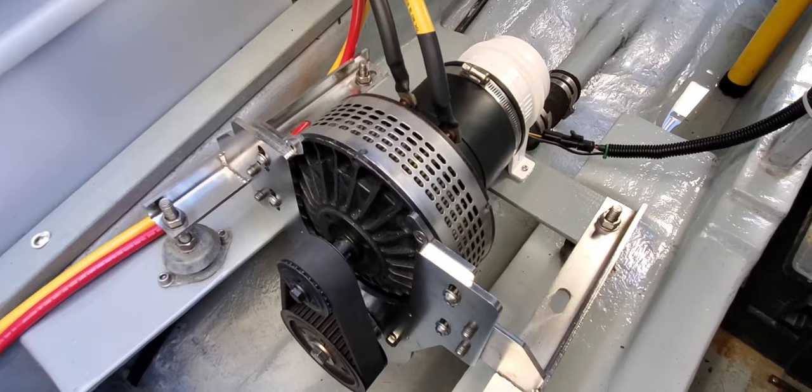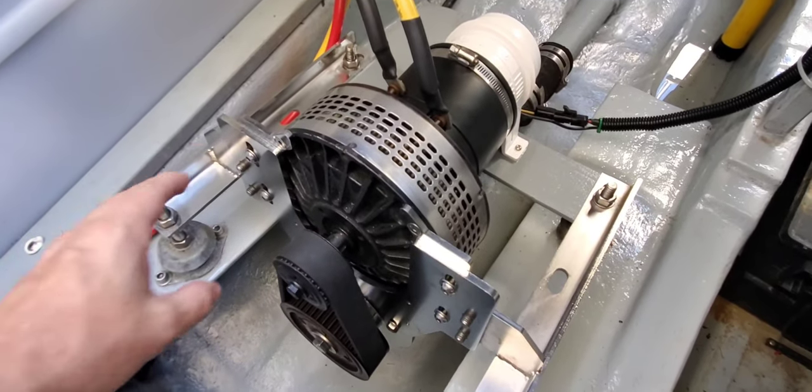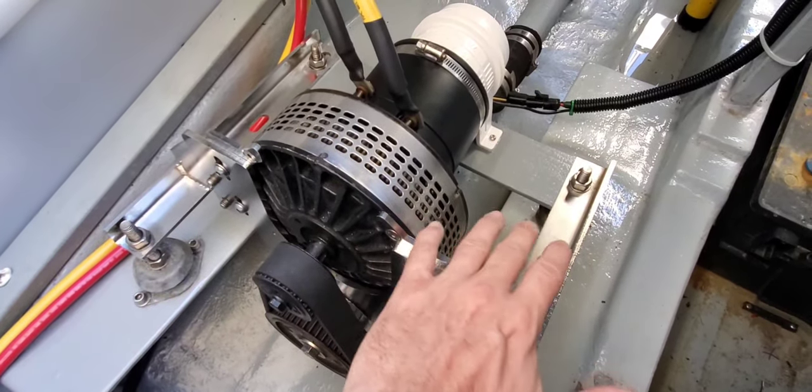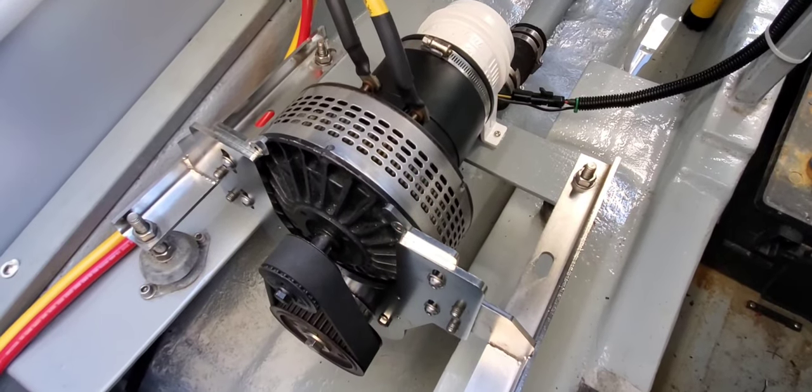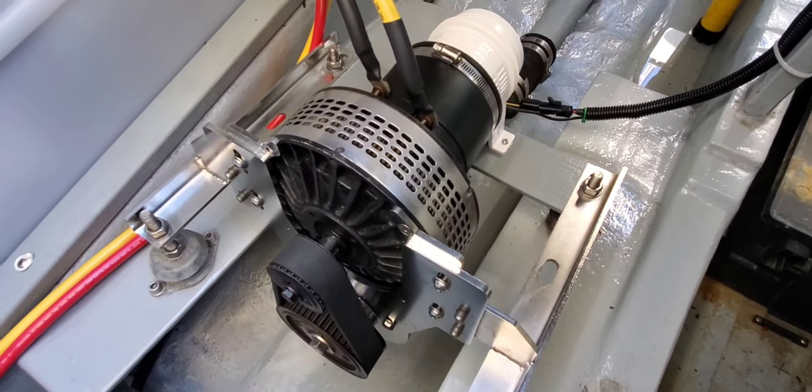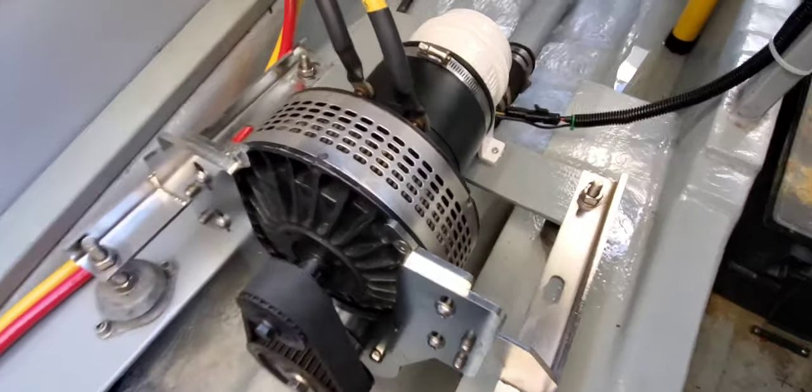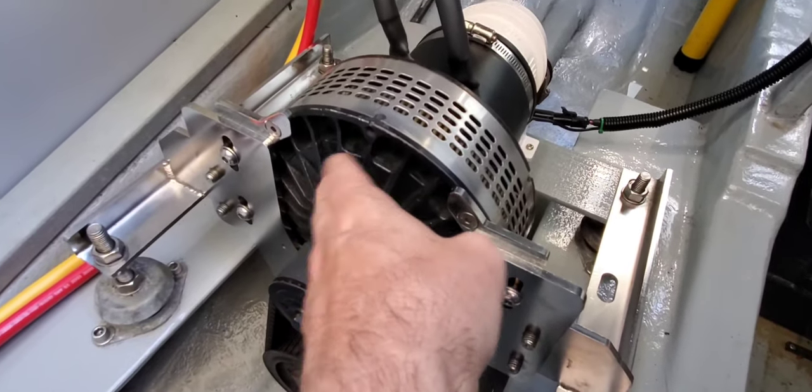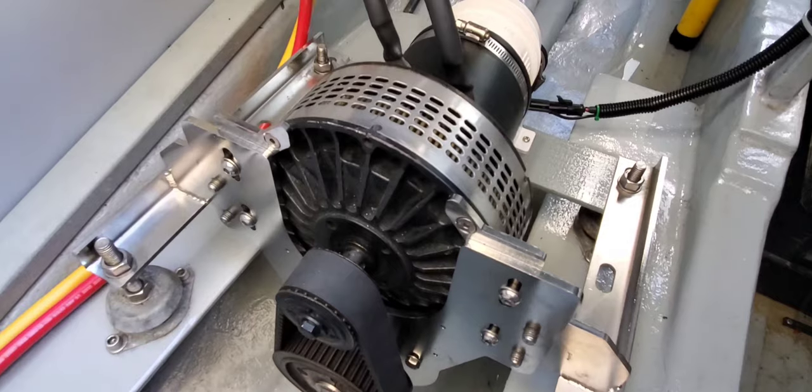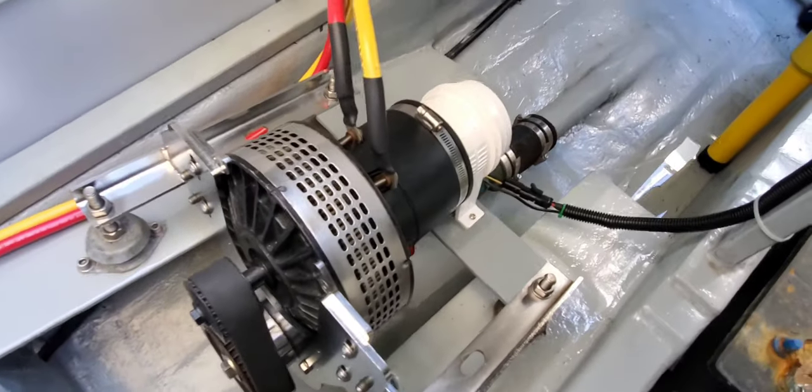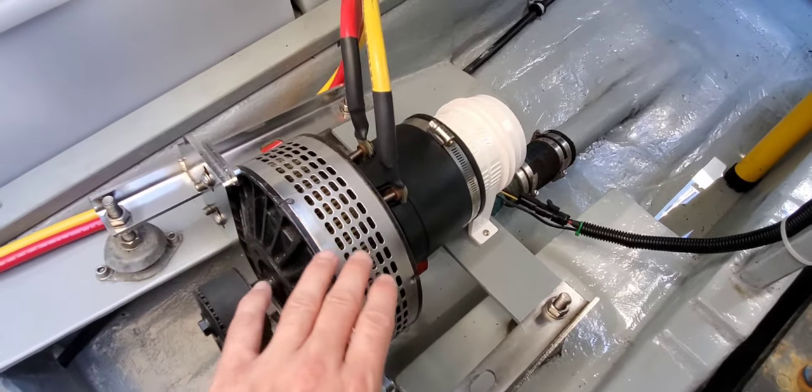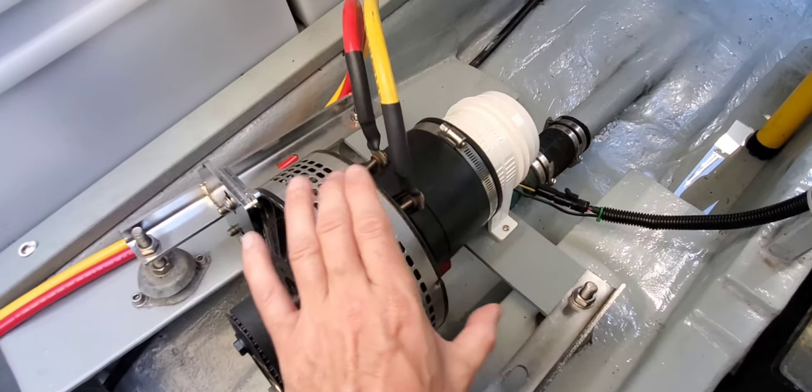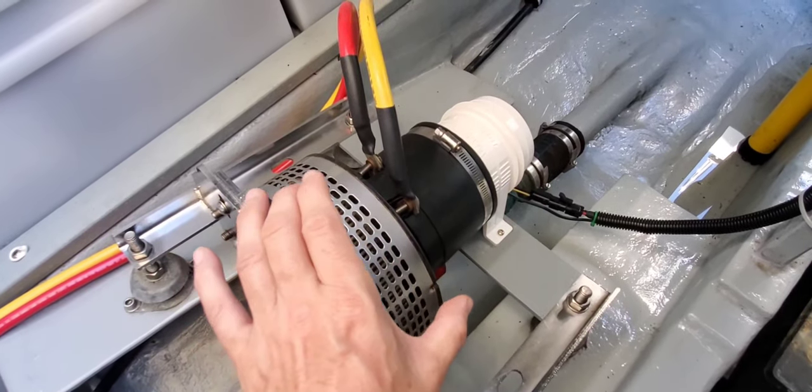This here is what they refer to as a pancake design. The Lynch motor has a perforated cover which allows for a lot of very good airflow and allows it to run continuous at a constant temperature. It also has some fins in the casting here, and I'm going to assume that that's for heat dissipation. We've also done a mod here at the back. Normally you don't have this blower fan setup—you just have a plastic cover that protects the brush holder.